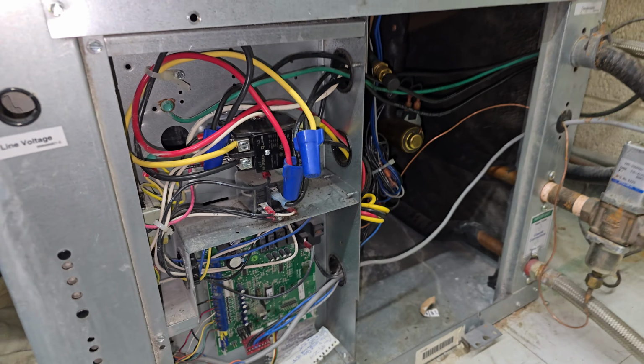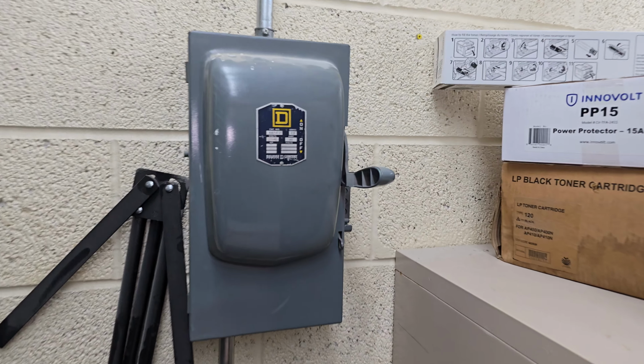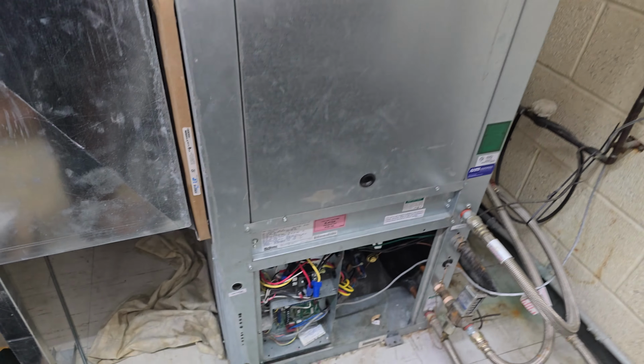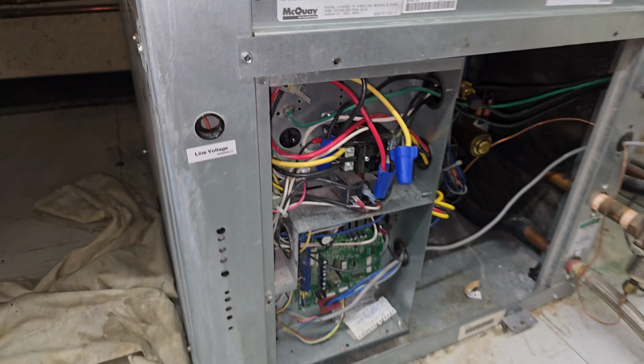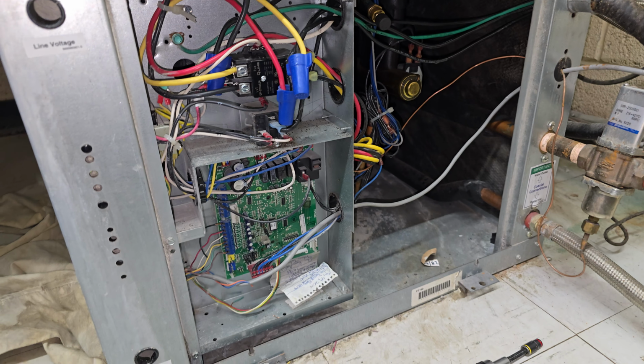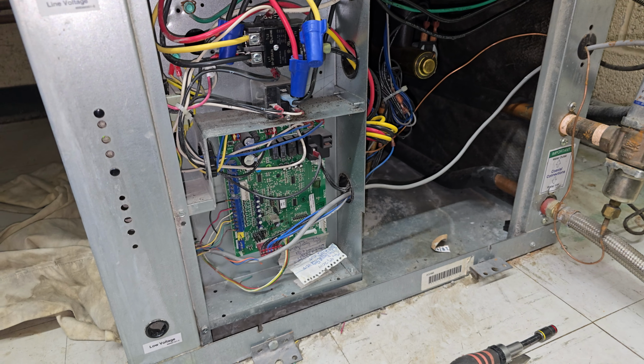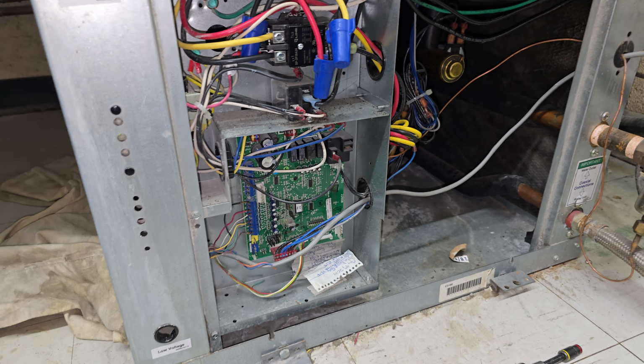So I'm gonna turn this unit on. Okay, so here's my breaker. So I'm gonna just turn it on. All right, so my unit is turned on. It's gonna take 3 minutes. The blower motor will kick in, but it's gonna take about 2 to 3 minutes for the compressor to kick in. So once the compressor kicks in, I'm gonna take an amps reading of the compressor.